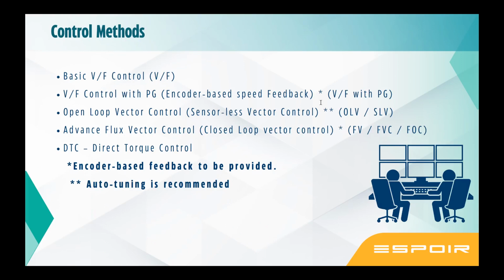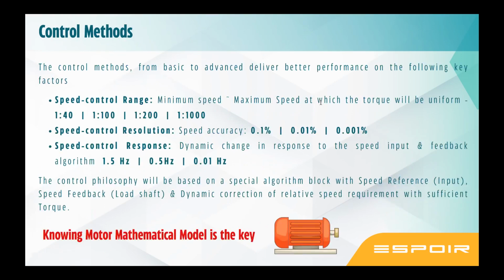All different control methods give 3 aspects of change in the system. One is it influences the speed control range, speed control resolution, and speed control response. These are the 3 aspects or objectives of selecting a proper control method. Let's come one by one. What is speed control range? What is the minimum speed, maximum speed you can achieve? Minimum speed achievement is very important, which is decided by the speed control method.